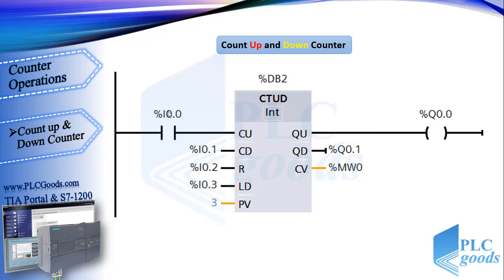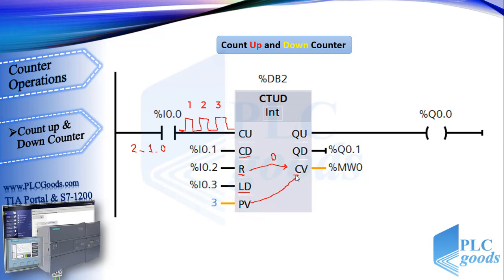Let's see how this simple ladder program works. For each pulse at the first input CU, the counter value increases — for example, from 0 to 3. At this moment, like a count up counter, because the current value equals the preset value, the first output QU will be on. After that, if we have three positive pulses at the second input CD, the current value decreases to 2, 1, and finally 0. The reset terminal can set CV to 0, and the load terminal copies the preset value to the current value. This counter has two outputs: the first output will be on if CV is equal to or greater than the preset value, otherwise it will be off.